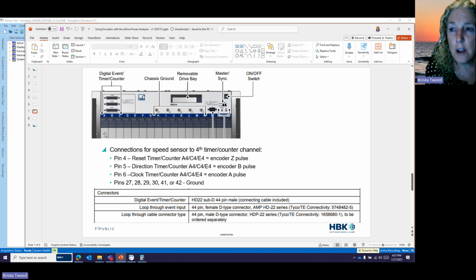So typically for eDrive, you will have power modules in slots A, B, and possibly even more. So I'm just going to focus in on the AB connector right now. Everything I tell you works the same for the CD connector and the EF connector, as long as you have those slots populated in that mainframe. So the fourth timer counter channel associated with those power modules uses pins 4, 5, and 6 on that digital input connector. Pin 4 is what we call reset, that's your Z pulse. Pin 5 is the direction, that's your B pulse. And pin 6 is the clock, and that's going to be your A pulse from your encoder. And then you have a variety of pins that you can use for that ground connector.